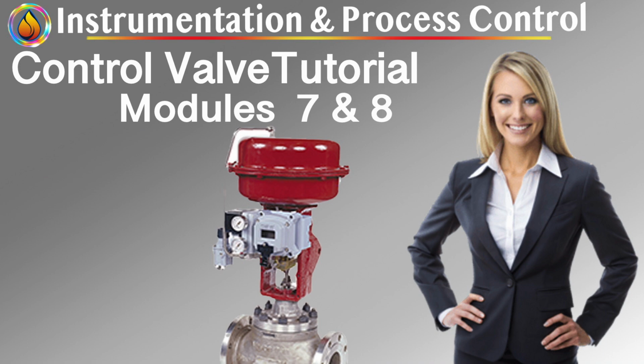Small signal versus large signal response. Valve dynamics are nonlinear. Small signal response governs disturbance rejection near set point. Large signal response governs startup, shutdown, and upset recovery. Common reality: valves respond sluggishly to small changes due to friction, and respond aggressively to large changes once friction is overcome. This mismatch produces limit cycles during steady operation and overshoot during set point changes. Designers who only test full stroke response miss the behavior that dominates daily operation.